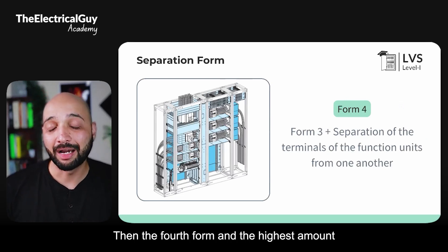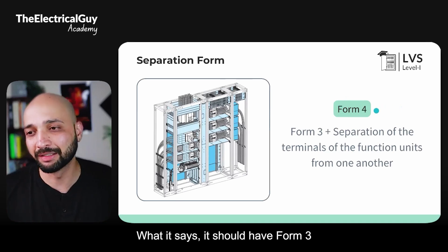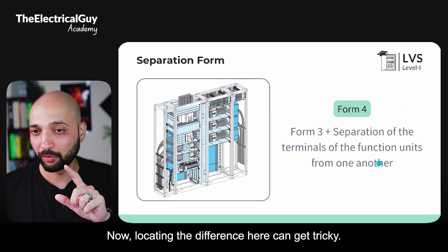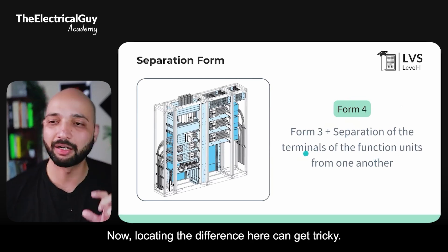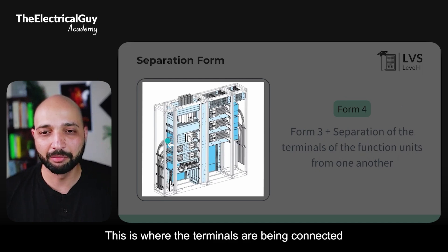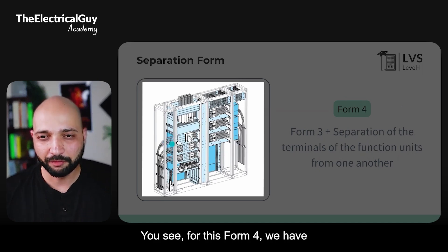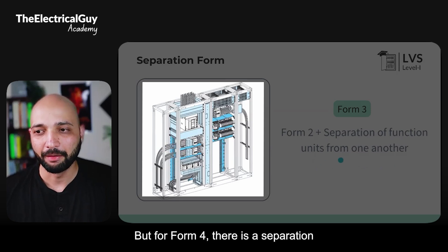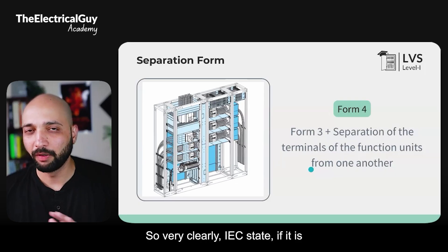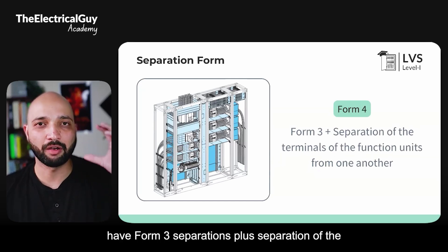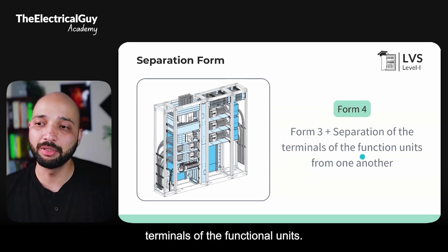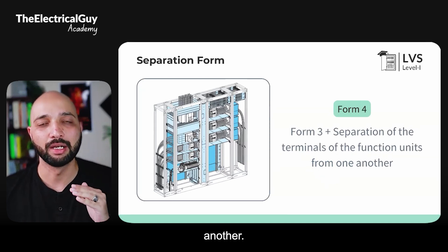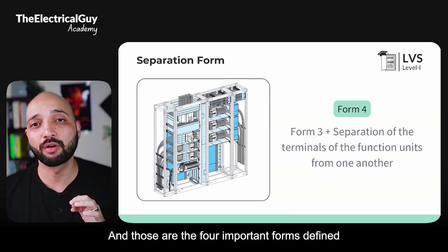Form 4 provides the highest amount of safety. It requires Form 3 plus separation of the terminals of the functional units from one another. Focus on the terminal connection area of the MCCBs — in Form 4 this area is separated, whereas in Form 3 it is open with no separation provided. Everything is insulated: all terminals of all functional units are insulated from one another. Those are the four forms defined by the IEC.